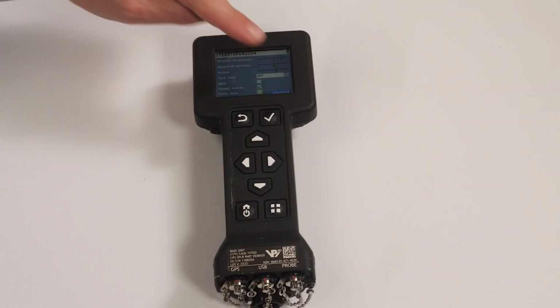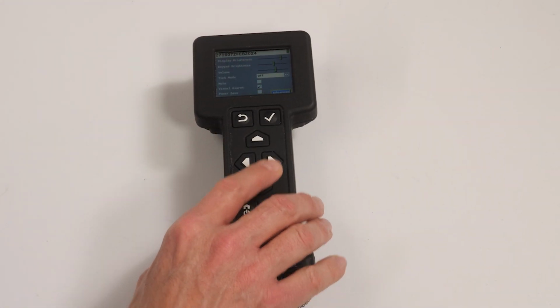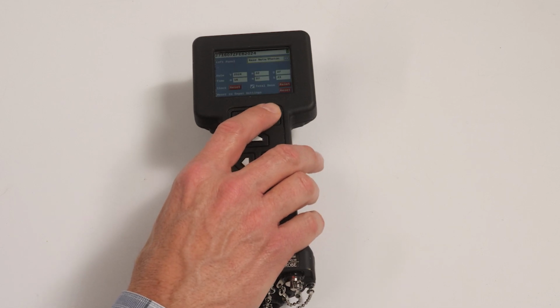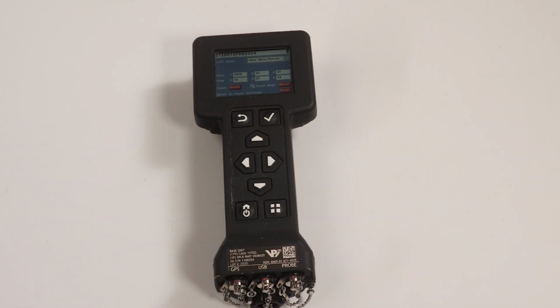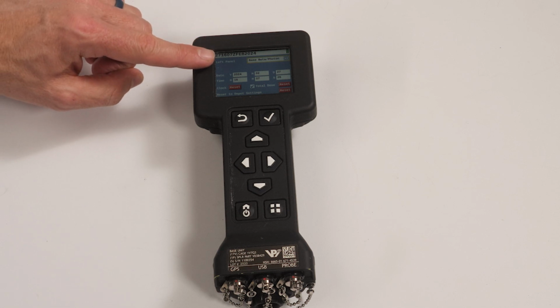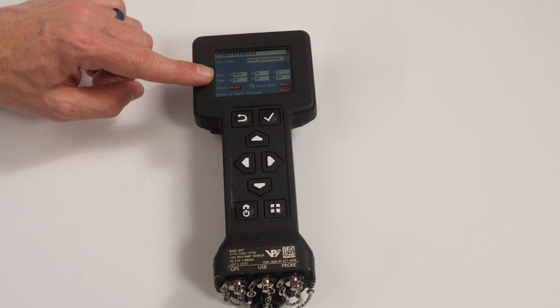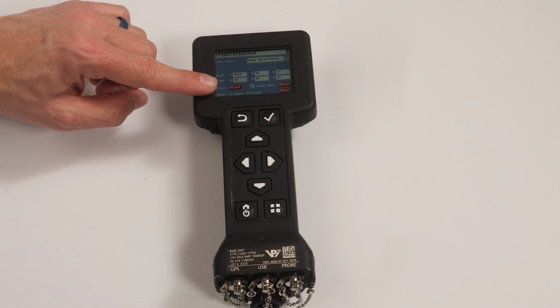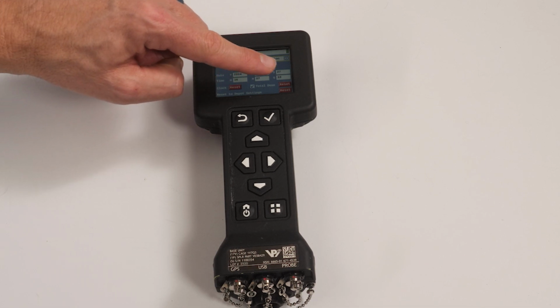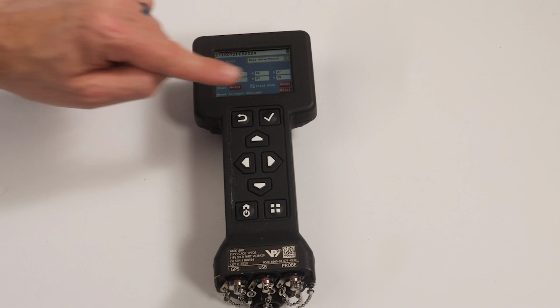Note that even in power save mode, the base unit will continue to monitor the radiation level. Any alert or alarm will cancel sleep mode and display the alert or alarm screen. At the bottom of the settings screen is the Advanced button. Highlight the Advanced button and press the Enter key to access settings that allow you to control what is displayed on the left panel and right panel of the home screen, the date and time, performing a clock reset, display of total dose, and reset to depot settings.